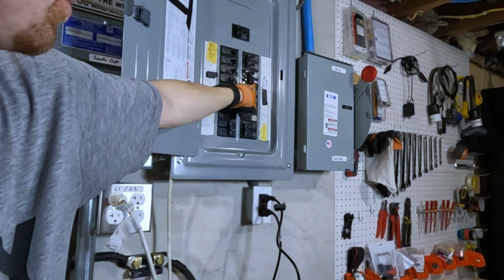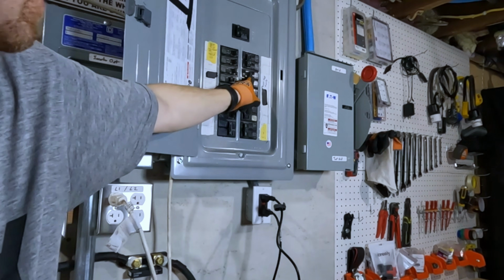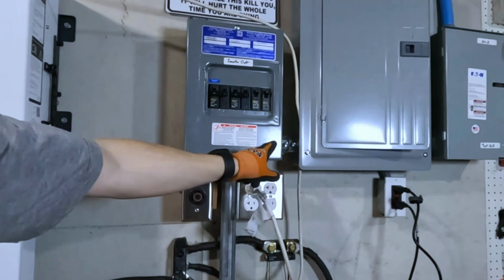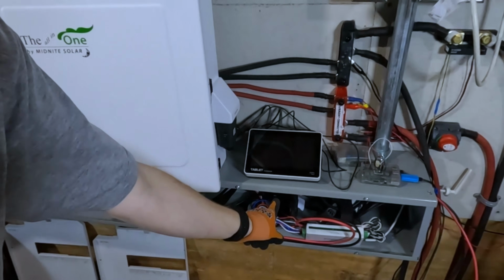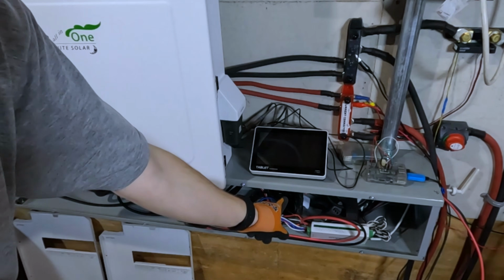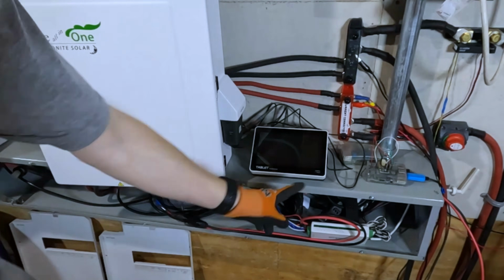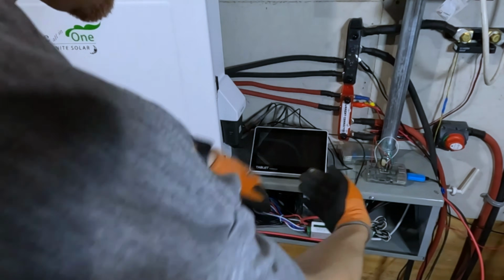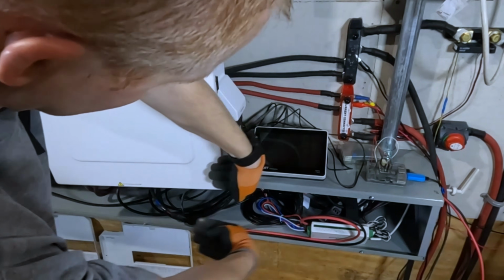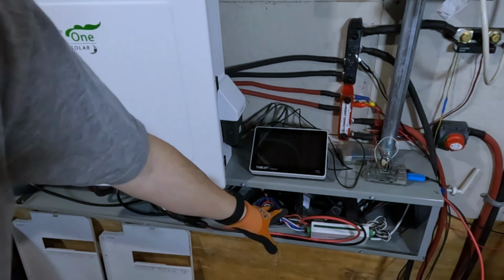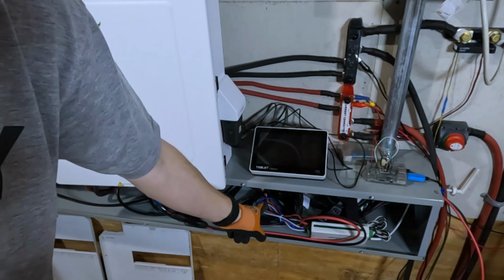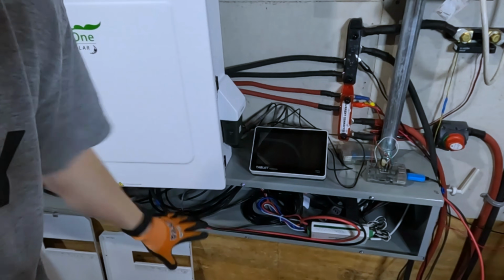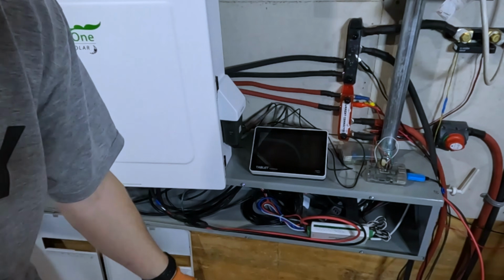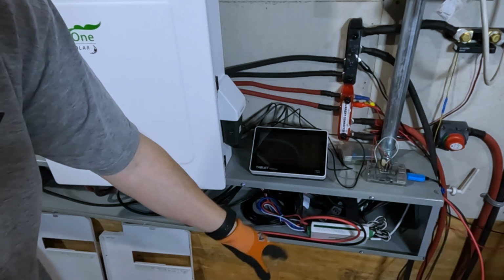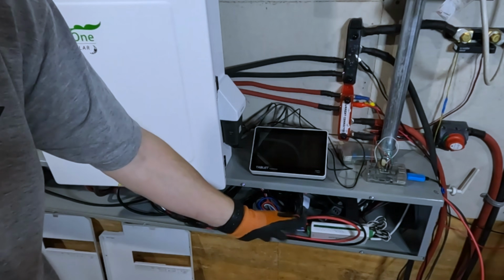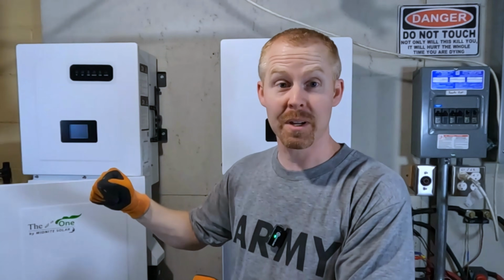I have 1 double pole breaker for my test wall. Those leads come from this panel, come over and down into that PDB for the AC input that we just saw. And so from there, I can then split and have it go to each inverter. So all my AC connections now are going to be down in here instead of having to run multiple lines to a critical loads panel. It drastically simplifies things. So let's get to the actual wiring.